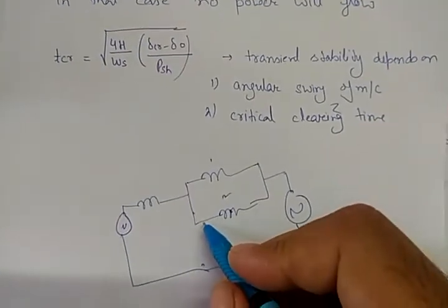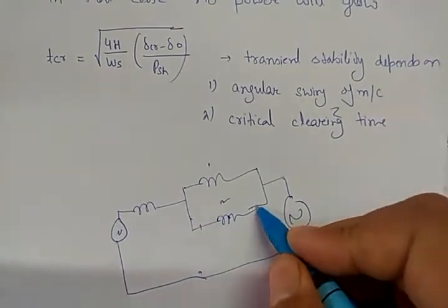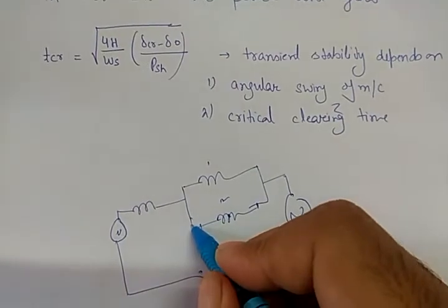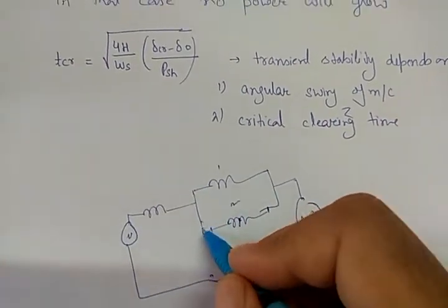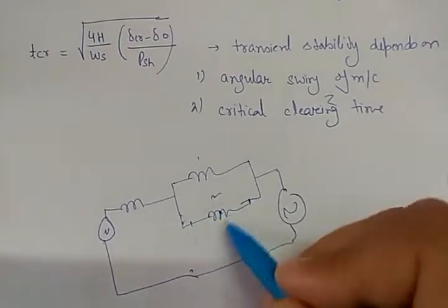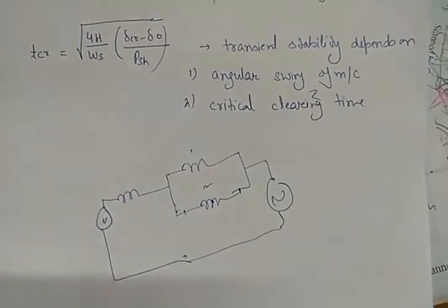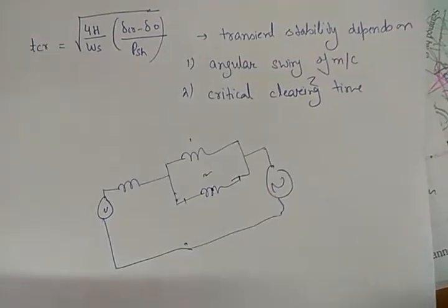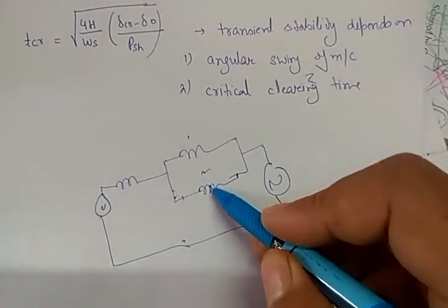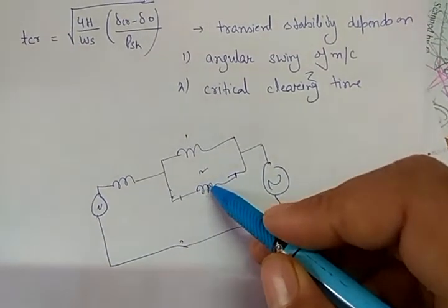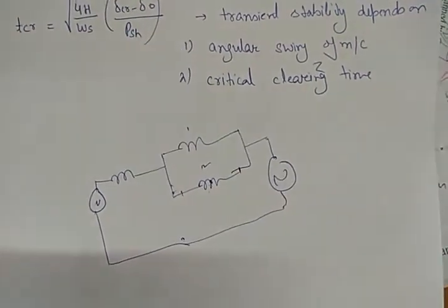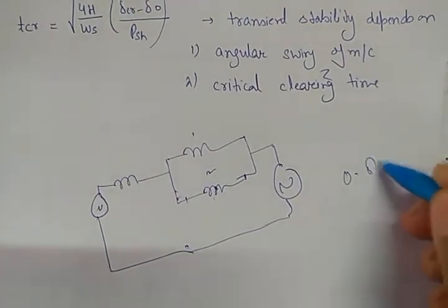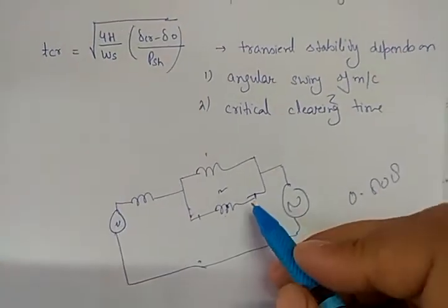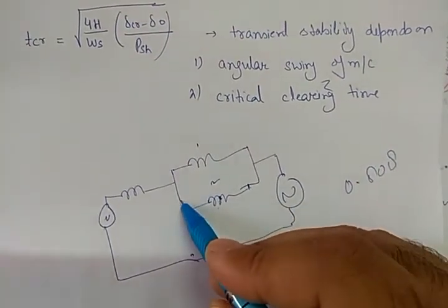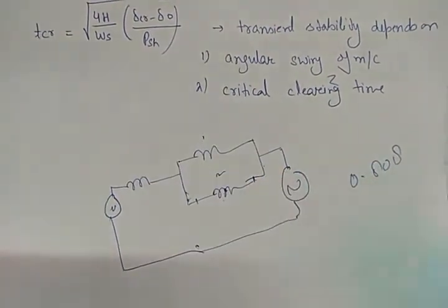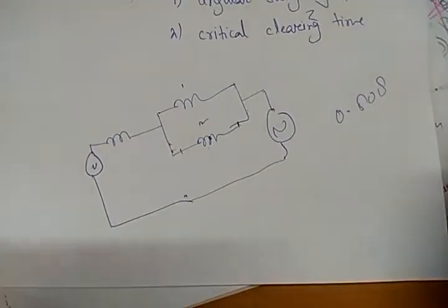But what will happen if the fault occurs at the extreme ends of the transmission line or on the bus where these transmission lines are connected? If it occurs on the bus, then no electrical power will flow. Electrical power will flow only if there is some impedance to the fault. At the center of the line, the circuit offers some impedance to the fault, so some electrical power flows, which was equal to 0.808 sine delta. But if the fault occurs at the extreme ends of the line or on any bus where the lines are connected, then no electrical power will flow in the system.